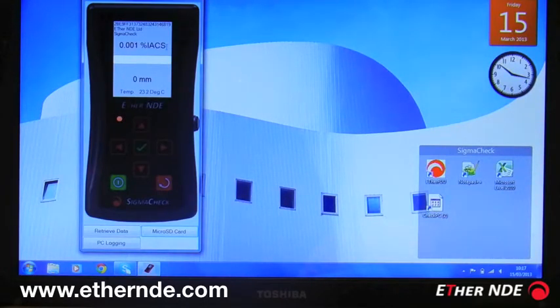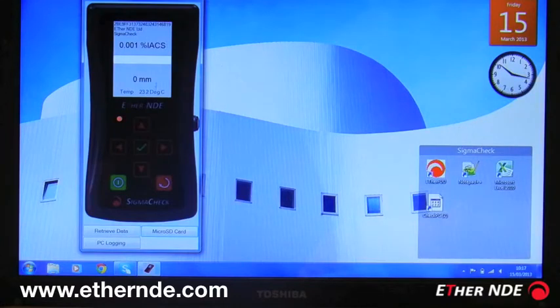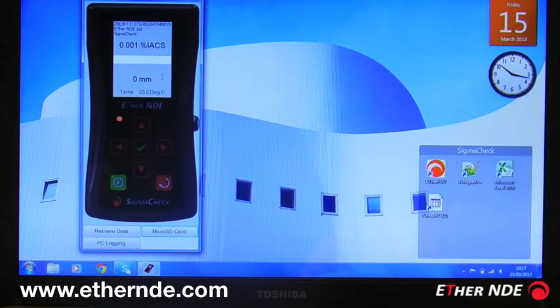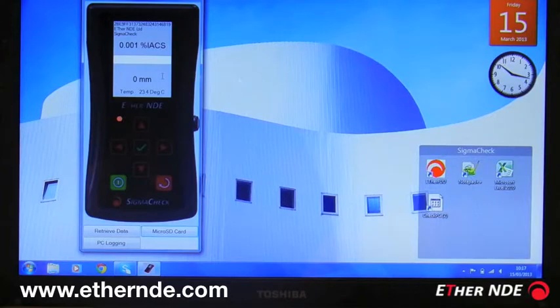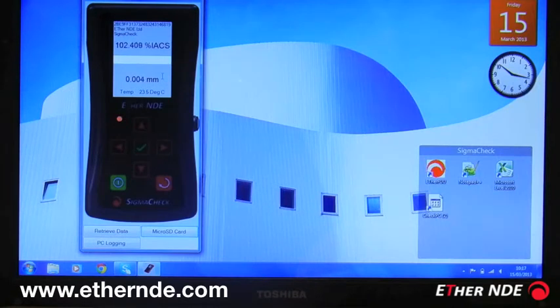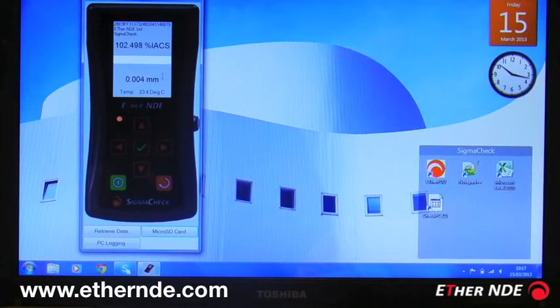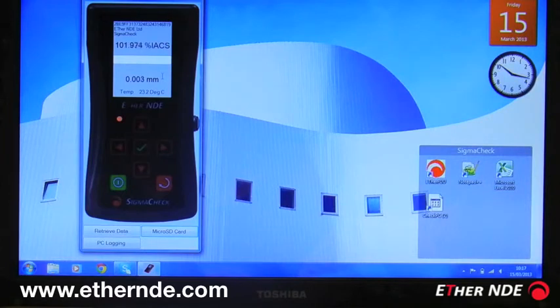Here we have a conductivity value, a lift-off value, and finally a temperature. Now this is real-time data being streamed from the SigmaCheck. If I now place my probe on a copper sample, you can see it's reporting the live IACS value, the lift-off, and the temperature.